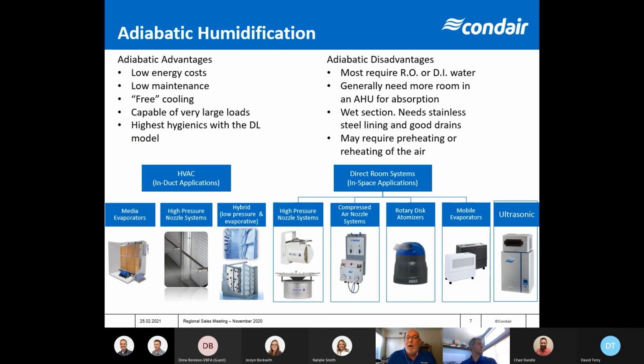When we run potable water, we will leave minerals behind, which will build up on the media. The media will need to be changed periodically. Now this product does not give us our best controllability, but we do have some modulation capability. We call it staged modulation. So we're turning sections of the media on and off to control how much cooling or humidity we want to generate. So it's very, very cheap to run though.